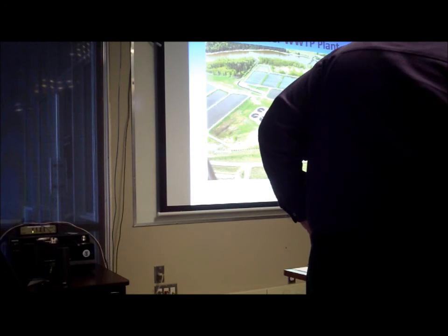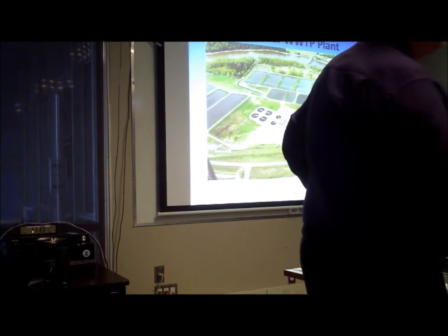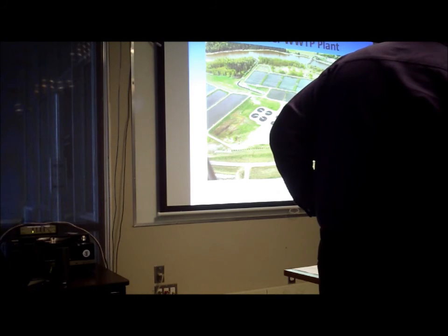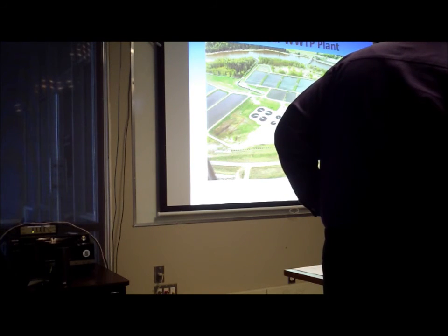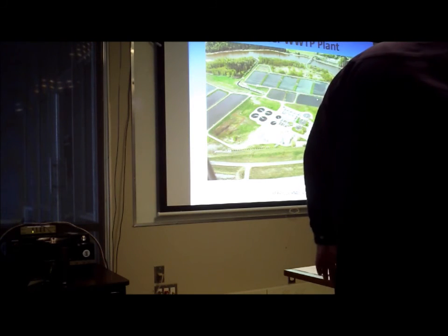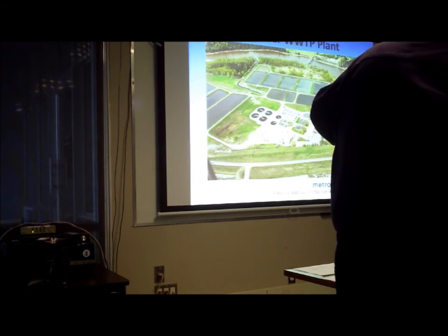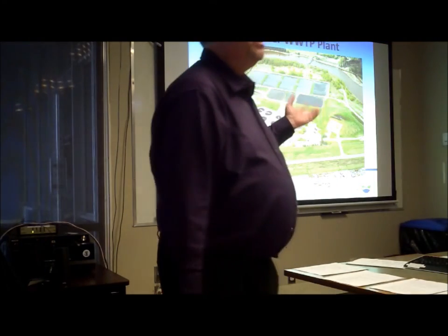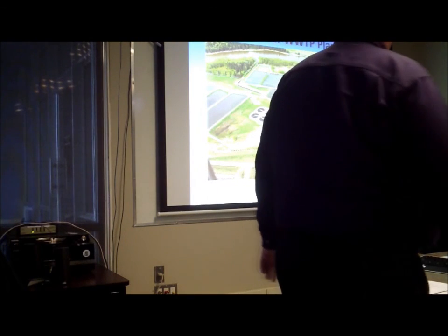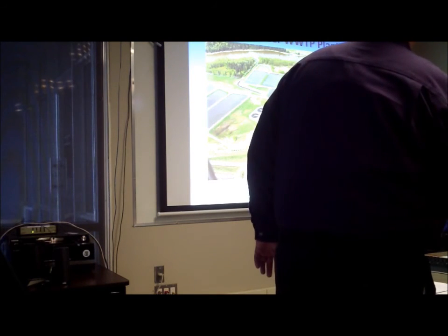These tubes here are Archimedes screw pumps, and that's what we used for lift pumps in this particular plant. So there was an overflow channel that went to the lagoons, and then they were all tied together. If we had these things empty, we actually had about 2 days flow capacity. So for extreme rain events and power outages, it was a real lifesaver.